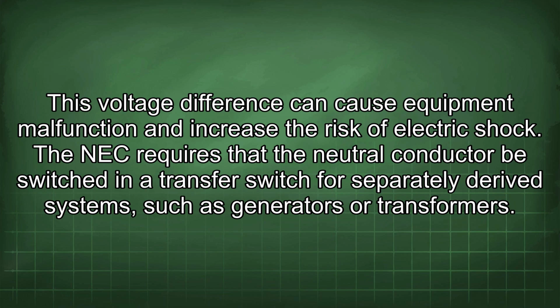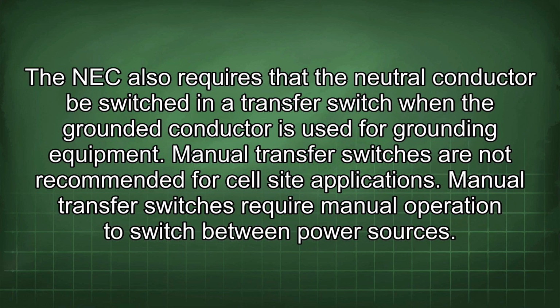The NEC requires that the neutral conductor be switched in a transfer switch for separately derived systems, such as generators or transformers. The NEC also requires that the neutral conductor be switched in a transfer switch when the grounded conductor is used for grounding equipment.